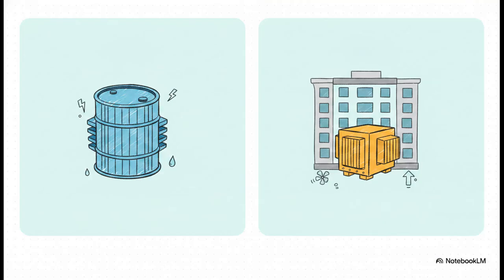You know, the golden rule of transformer engineering is actually pretty simple. If you put the wrong transformer in the wrong place, it's going to fail in month 6 instead of year 20. Seriously. So, how do we actually choose? Well, on one side, you've got oil-immersed transformers. These use a fully sealed tank where oil, either mineral or synthetic ester, acts as both an incredible insulator and a coolant. And because of that, they have a really compact footprint. The catch? Oil is combustible.